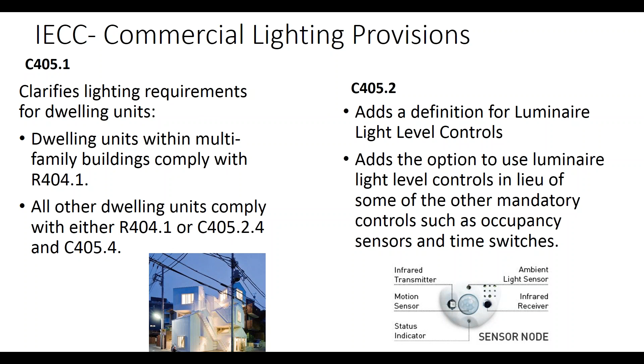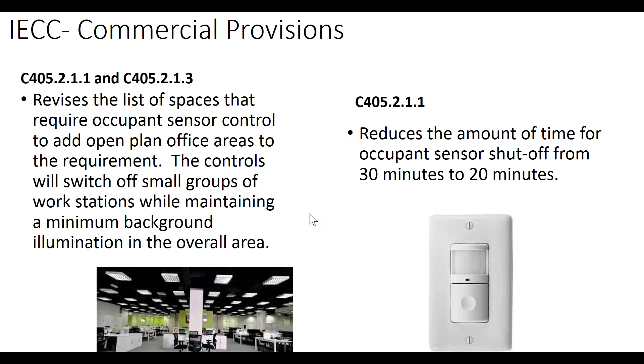Then they brought in requirements for open office spaces because these were left out in the code, just talking about these open office spaces. When should the light shut off, and how big can the space be that you can control under one light or one sensor or whatever, and allowing some minimal level of safety lighting while if these people aren't here but these people are, these shut off. So there's some different requirements in there. There's some new provisions for open office lighting. And then there's a change in occupancy sensors. It used to say all occupancy sensors shut off within 30 minutes of people leaving the building. Now it's 20, or the space.